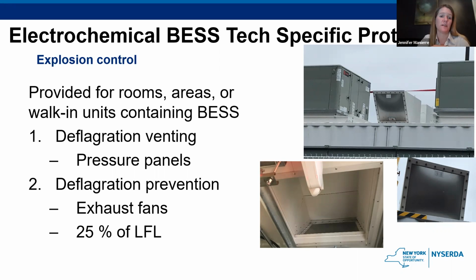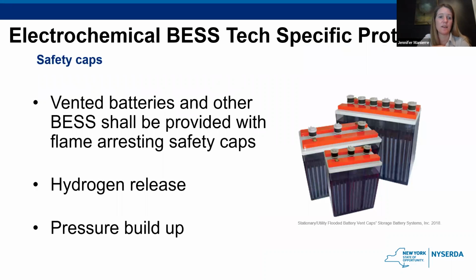And they should also have deflagration prevention. So exhaust fans are an option, just like we were talking about on the slide before, where you limit it to 25% of the lower flammability limit. So these are the two options for explosion control. You could even do both if you want. Any batteries that are vented, for example, lead acid batteries that have a hydrogen byproduct just as part of their charging and discharging process, so they're vented. For any of those types of batteries, they need to have safety caps that prevent any flames that might be near them from going back into the battery. So they'll let the battery vent out, but prevent flames from going in and making things worse.